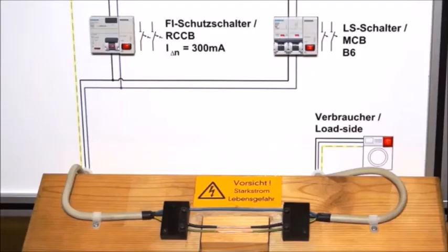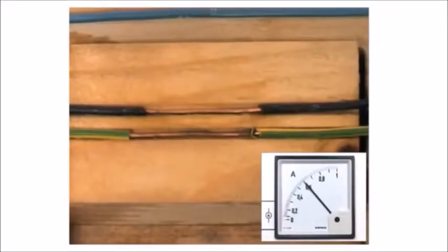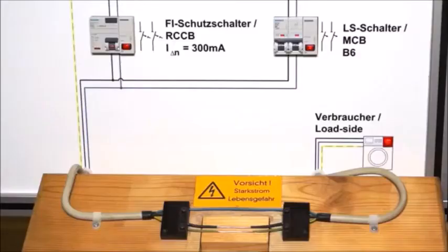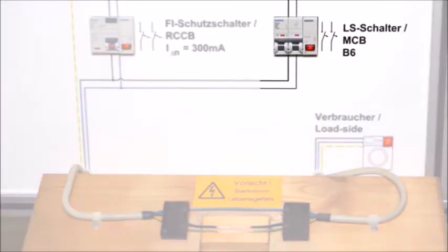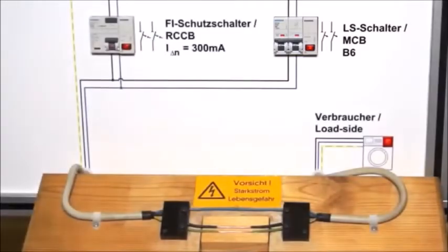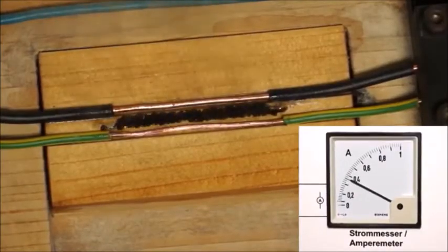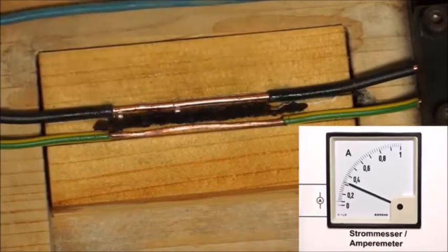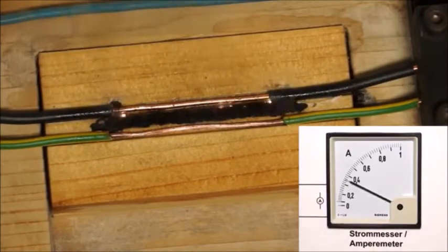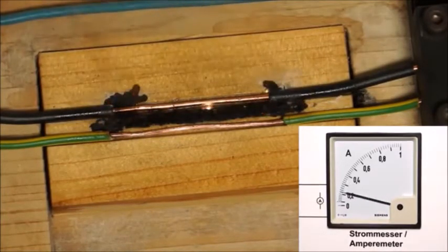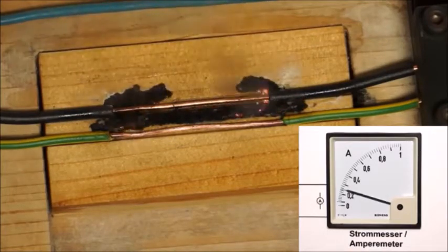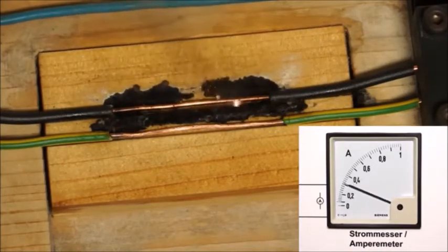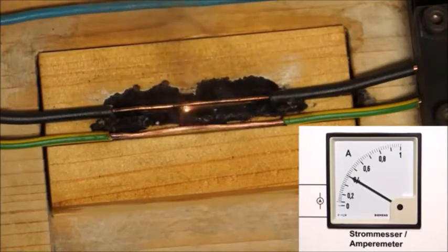The second test clearly shows why residual current operated circuit breakers are so important. A fire can start when the current flowing at the fault location is just 300 milliampere or so. In this case, a miniature circuit breaker cannot protect against electrically ignited fires as it only trips at much higher currents. The insulation fault simulated here can easily lead to a smoldering fire or even a full blaze. RCCBs with a rated residual current of less than 300 milliampere could prevent this fire and consequently provide preventive fire protection.